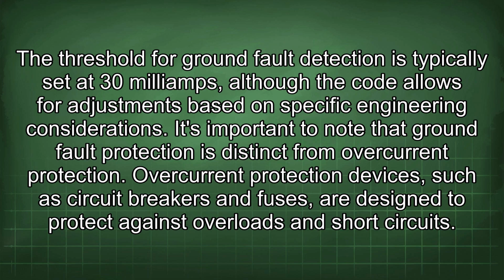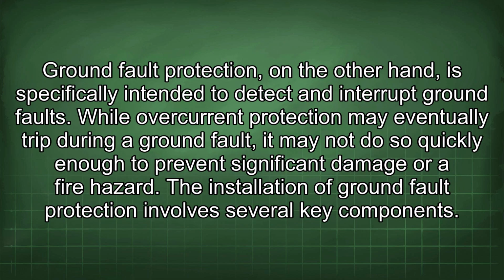The threshold for ground fault detection is typically set at 30 milliamps, although the code allows for adjustments based on specific engineering considerations. It's important to note that ground fault protection is distinct from overcurrent protection. Overcurrent protection devices, such as circuit breakers and fuses, are designed to protect against overloads and short circuits. Ground fault protection, on the other hand, is specifically intended to detect and interrupt ground faults. While overcurrent protection may eventually trip during a ground fault, it may not do so quickly enough to prevent significant damage or a fire hazard.